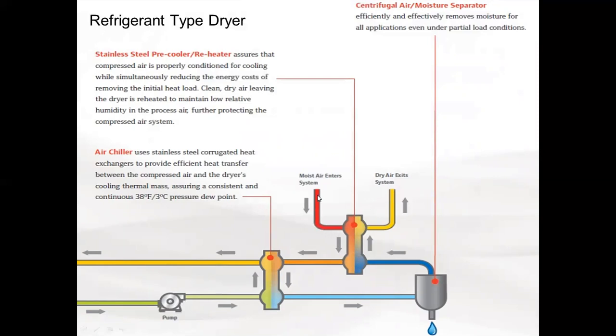so we don't get condensation in the pipes. And then the red is the compressed air, moist, saturated, coming in from the compressor. This is where it gets preheated, and then it comes down here to the main heat exchanger where it is cooled down to the 35 to 38. And then it travels over here to the moisture separator, so we get the bulk of the moisture out here. And then it goes up for preheating and out to the system. So, you know, that's pretty good.